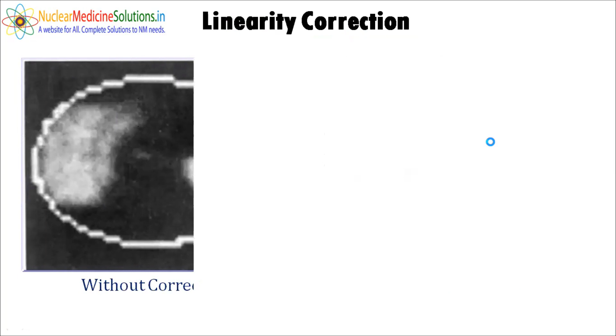Second comes the linearity correction map. As you know, a SPECT or gamma camera is not linear. Because of this non-linearity of the gamma camera, there is a difference between the estimated location and the measured location. And because of that, we are getting wavy lines in the image. So to remove these wavy lines from the image, we create a linearity correction map. After applying this linearity correction map, we have minimized the difference between the estimated and the measured location, and like that we are removing the wavy lines from the image.